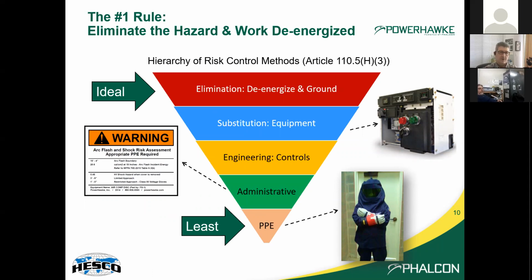PPE is the last resort. I say this in our training classes: PPE is not a Superman cape. It will not protect people from all bodily harm and injury. As a matter of fact, PPE is designed to limit the exposure to the human inside of it to less than a second-degree burn. So if you're involved in one of these flashes in proper PPE, you can still very well end up in the hospital, but with a survivable, non-life-threatening, non-permanent injury.